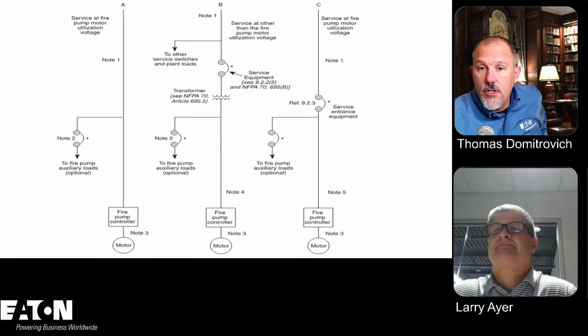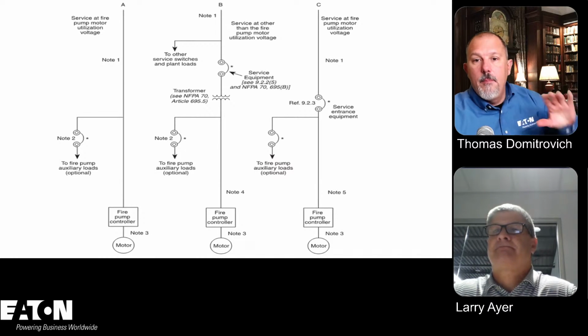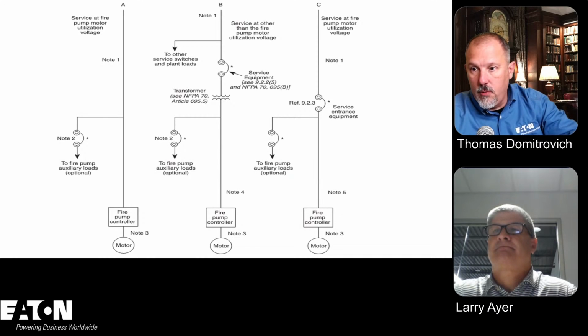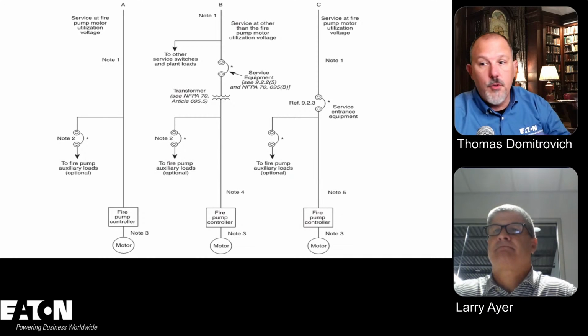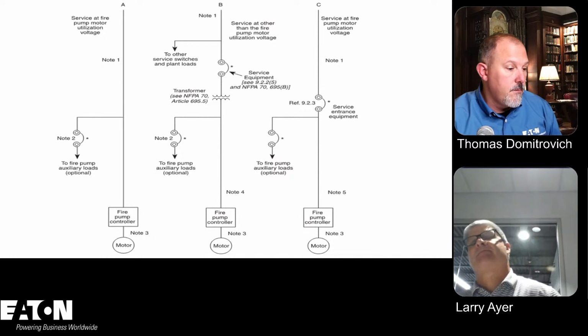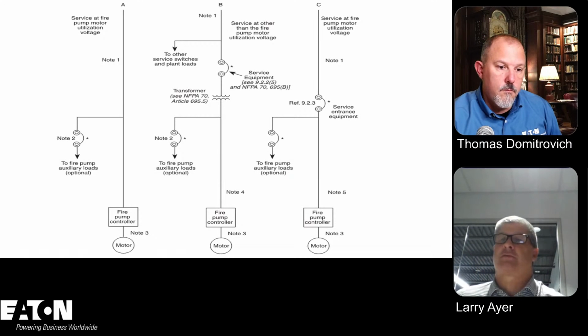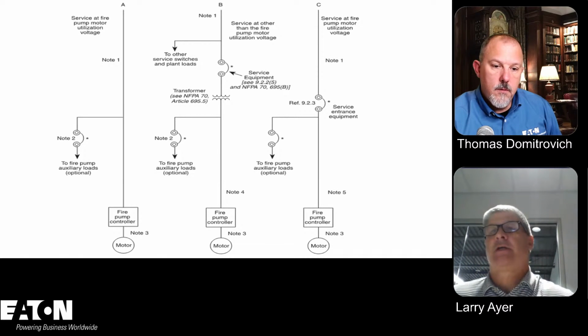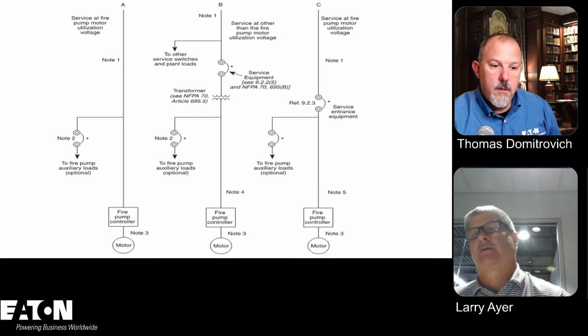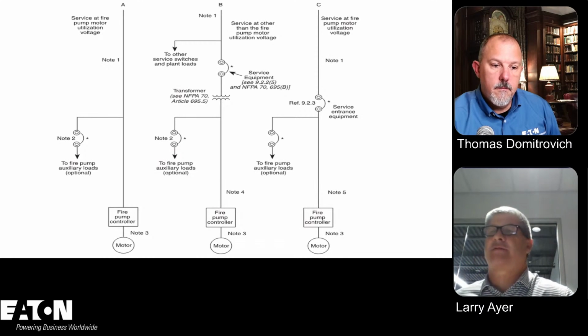Correct. Then there are no reliability requirements for that auxiliary equipment. If you wanted to pull it off of wherever, you can. But normally you pull it off that same feed because you've got it there. Well, what I'm saying is that for auxiliary loads like the pressure pump or jockey pump, those are such smaller loads that, like Mather said before, I've never really seen one tapped off. I've always seen them have a separate branch circuit for those loads.